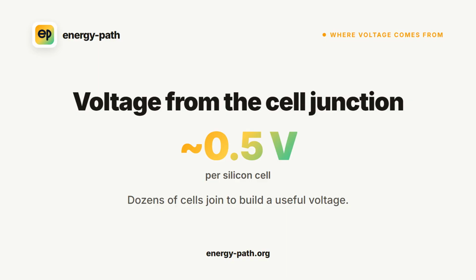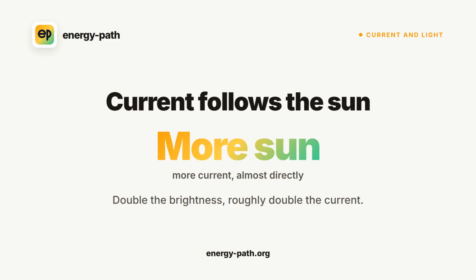Current is the rate of charge flow, measured in amperes. In a panel, the current rises and falls almost directly with the sunlight. Double the brightness, and you roughly double the current. Voltage behaves differently. It changes only a little with sunlight, but a lot with temperature. As a panel gets colder, its voltage rises, and that cold case sets the safe limit for a string.